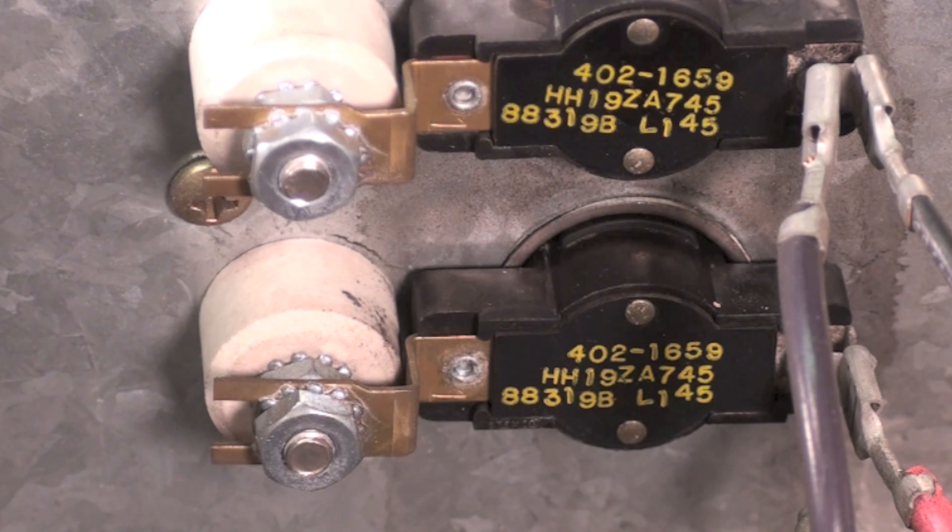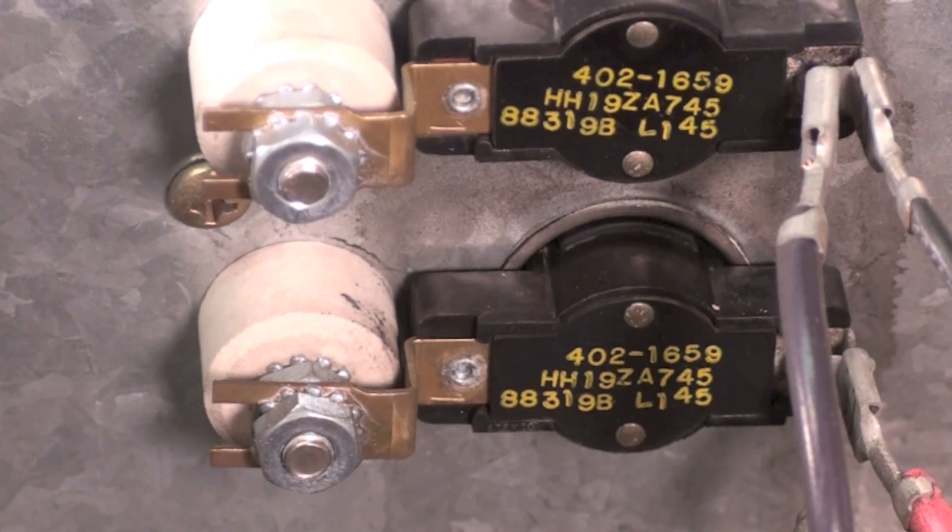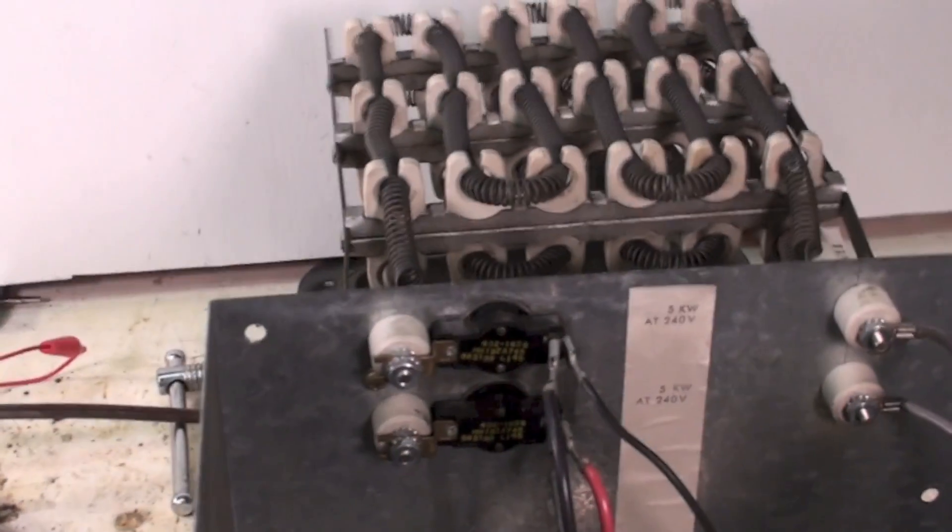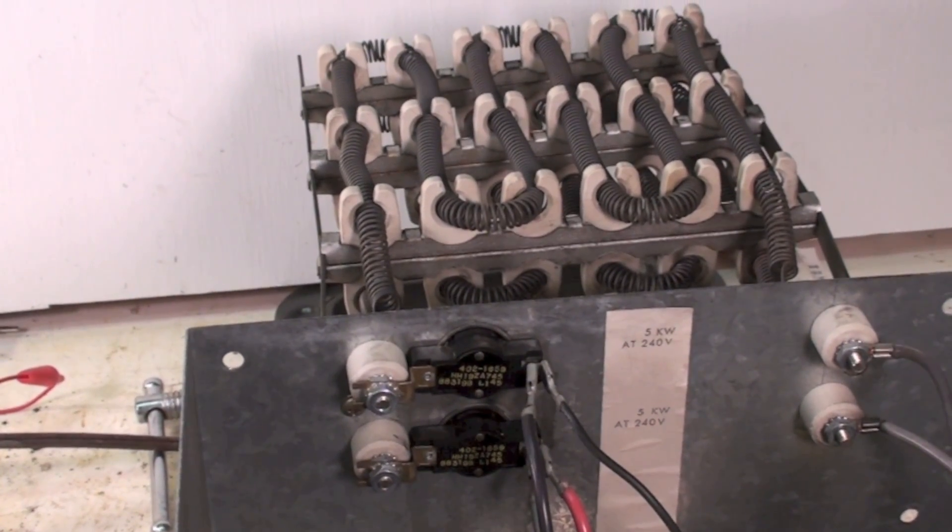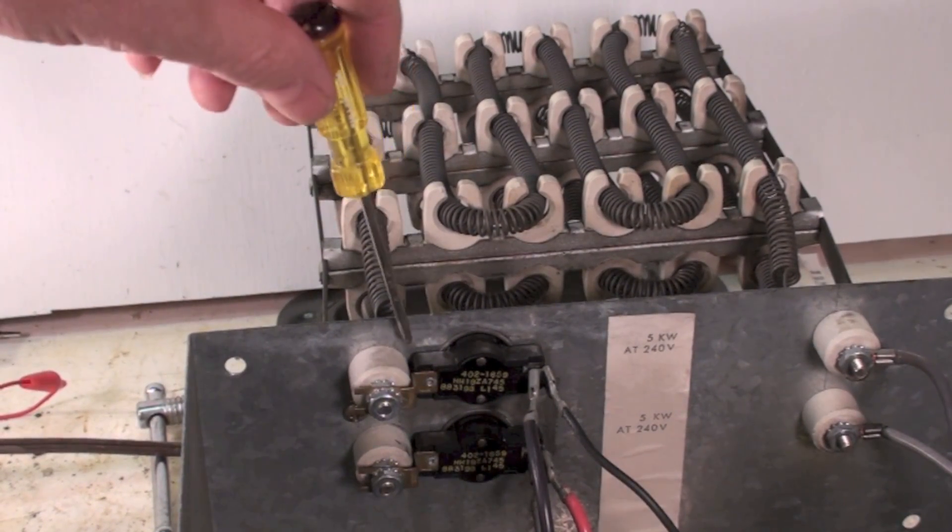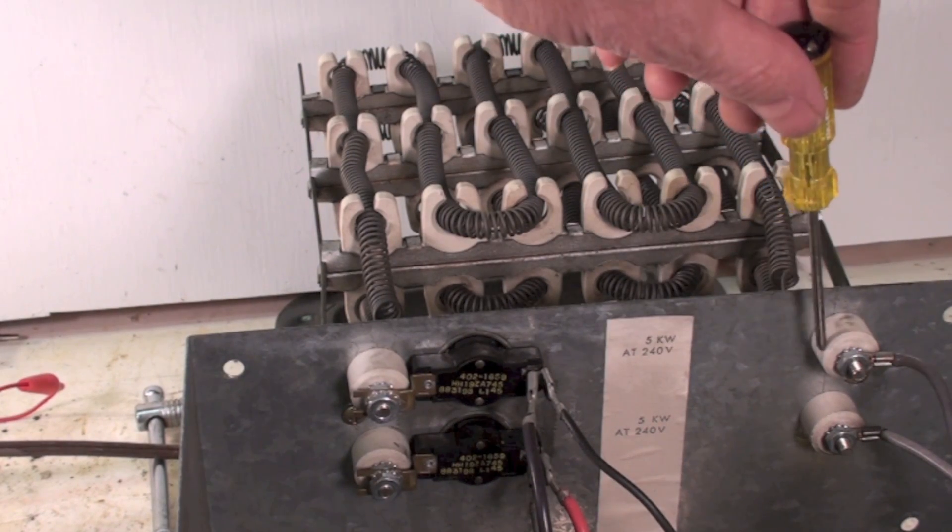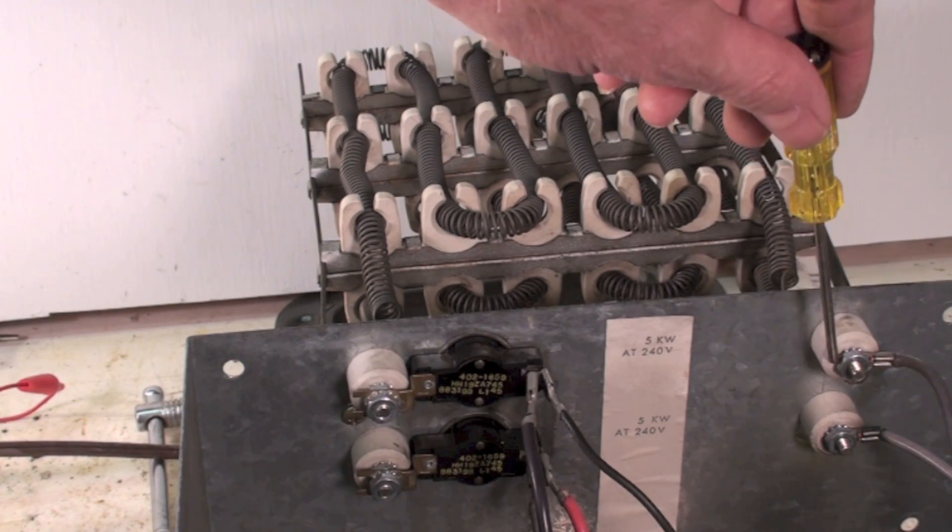This particular unit is a little bit odd. On this one, Carrier did this and I'm not sure why, but there's usually a fuse. It may be mounted like right here in series - it's a high temperature fuse and it blows and shuts it off.